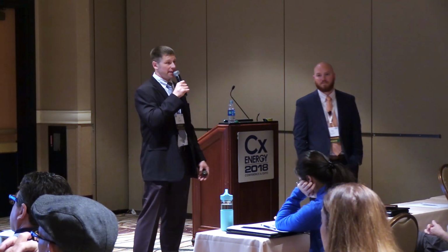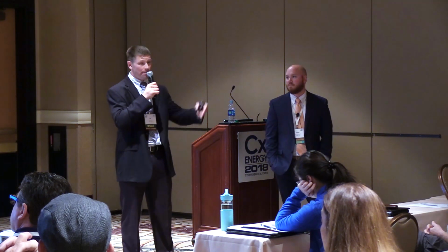For example, the facility with the so-called rain event. They wanted it to stop. So, we wanted to get in there, figure out what's going on, and fix that for them. But afterwards, they wanted us to continue on and see what else was going on in the facility, and we continued, and we did 100% testing of that particular facility. We did go lab by lab by lab after we commissioned the air handling units and the exhaust fans and everything. And so these are the deliverables a lot of times you're going to do.